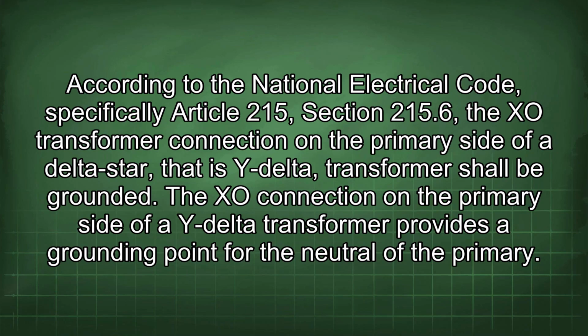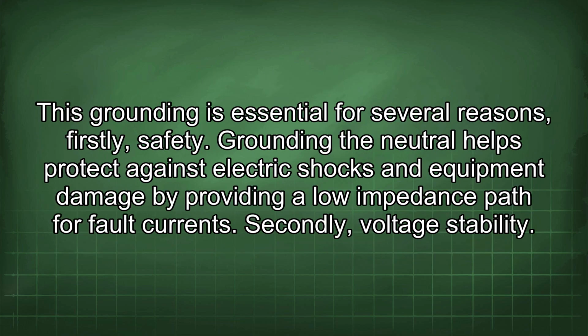According to the National Electrical Code, specifically Article 215, Section 215.6, the X0 transformer connection on the primary side of a delta star, that is Y delta transformer, shall be grounded. The X0 connection on the primary side of a Y delta transformer provides a grounding point for the neutral of the primary. This grounding is essential for several reasons.